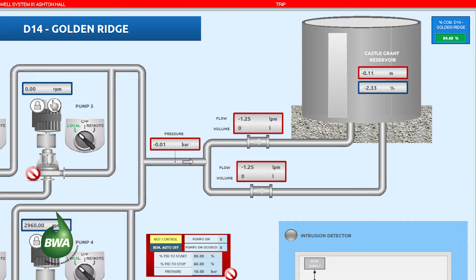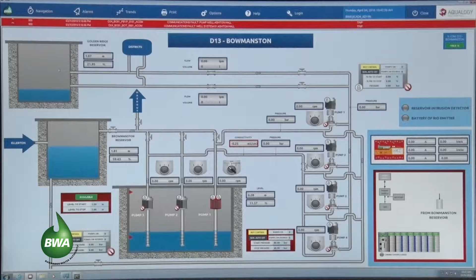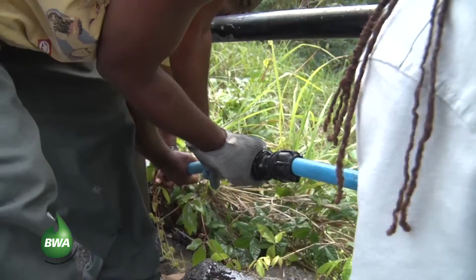With SCADA, you'll know if there's a leak from a drop in pressure, which shows directly on the system. Depending on the position of the burst, you can adjust the set point so persons can still get water at lower elevations while it's being fixed, or you can have a shorter response time by stopping the station from wasting water at the leak, going to SCADA and stopping the pumps while distribution fixes the burst.